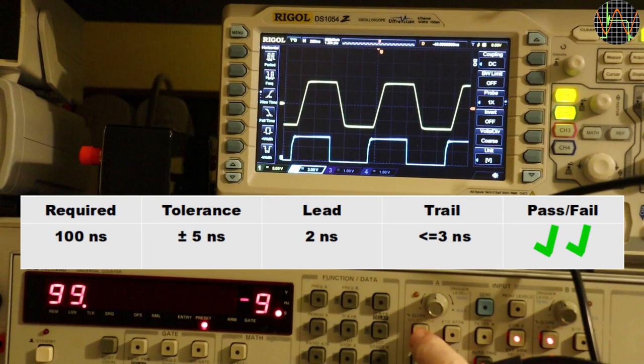All the while the procedure was using the same values for lead and trail but they don't have to be the same. On this generator, they are not totally independent from each other but it is completely possible to just have a far greater lead time than trail as you can see and of course you can do the same for trail. Overall with one slight excursion the lead trail time is okay and I decided to leave it alone.